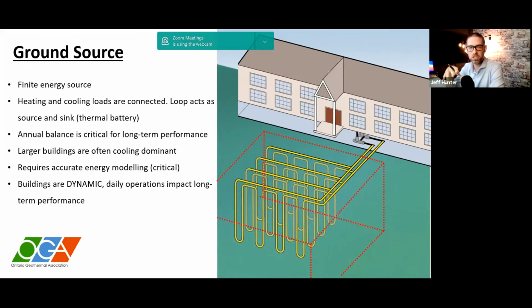The major difference between a conventional system and geo is that our heating and cooling loads are now connected, with the common source being the loop. The loop acts as our thermal source for energy in the wintertime, and as our thermal sink in the summertime - a common source. It's like a thermal battery where you're charging it up in summer and discharging that energy in winter. So that annual balance is absolutely important.